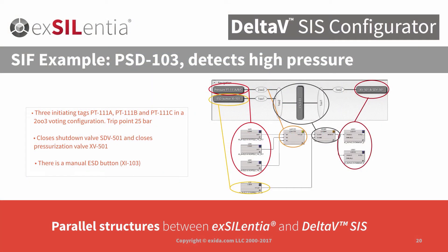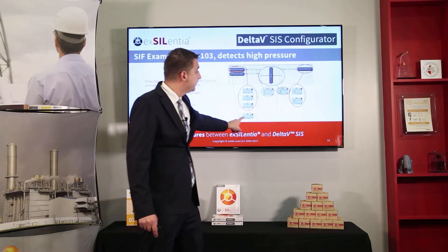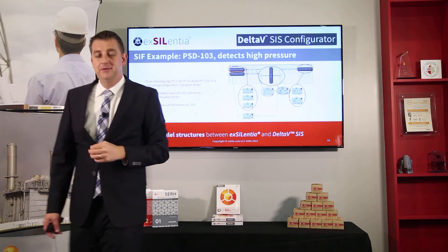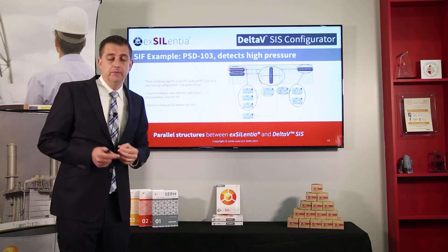Let's look at it in a little bit more detail. I have a very simple safety instrumented function here. It consists of a voting arrangement — two out of three transmitters and a single ESD push button — that go into a logic solver driving two outputs. We can see an analog voter block here with three inputs, representing my two-out-of-three voting.